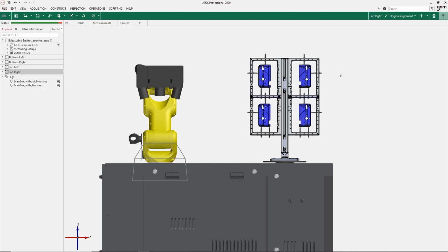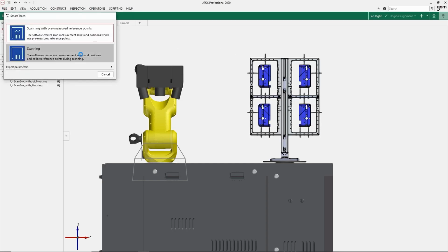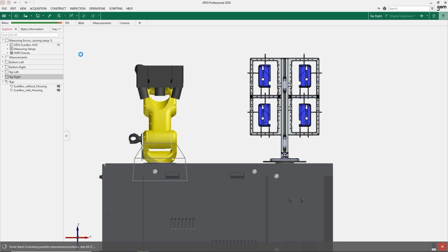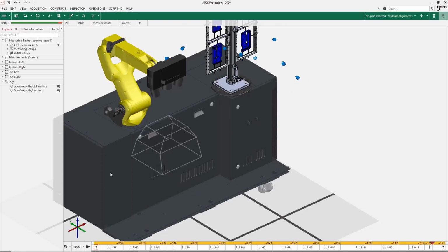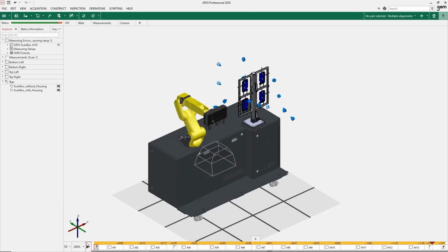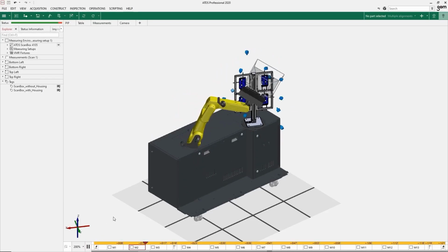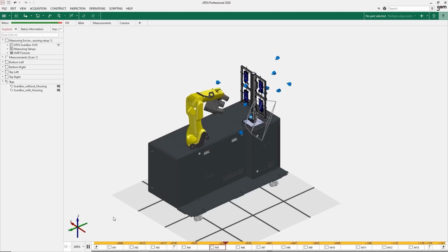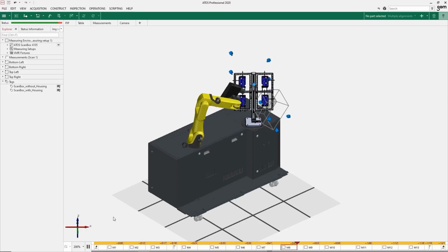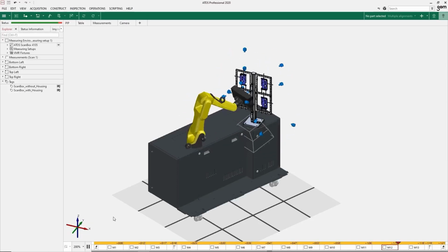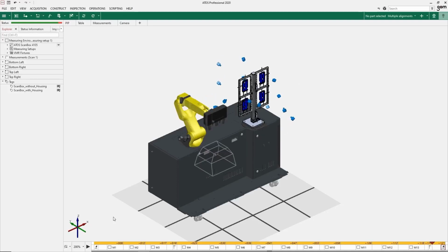Linked to the CAD file is an inspection plan. This could be loaded as PMI data straight out of the CAD file, or could be created by the inspector. Now that the software knows which features need to be inspected, we just need to start the Smart Teach procedure. In just a few seconds, all of the necessary sensor positions to scan the part are calculated. We can then finalize the procedure with an optimization, which will define the fastest route covering all the needed sensor positions. We're now ready to start the robot and let the ATOS Q scan these parts.